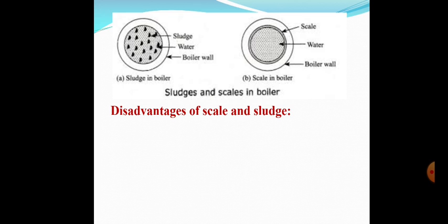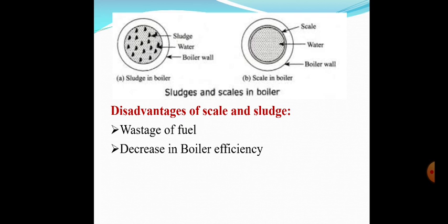Following are some of the disadvantages of scale and sludge formation. The first one is wastage of fuel: scales are bad conductors of heat, acting like a coating and insulating material on a metal surface, which reduces the rate of heat transfer from the boiler to water, causing excessive heating and wastage of fuel. The second one is decreased boiler efficiency: excessive scaling and sludge may cause clogging of tubes, reducing water circulation and impairing the efficiency of the boiler.